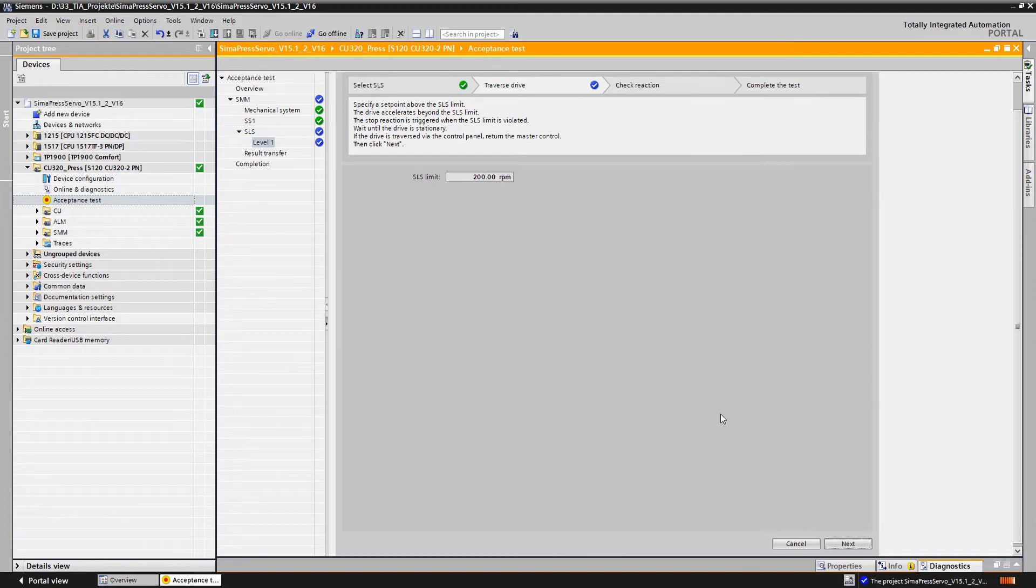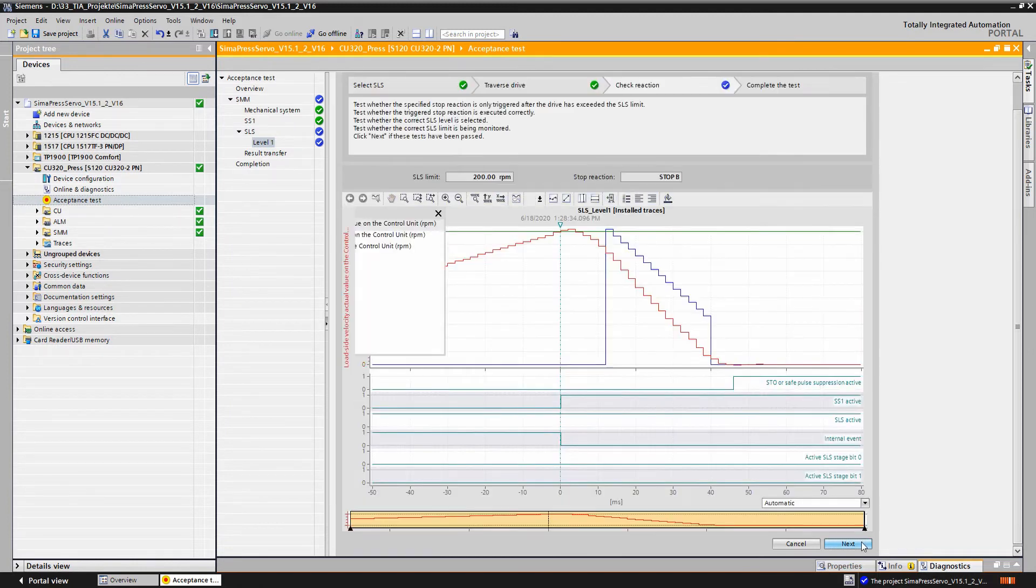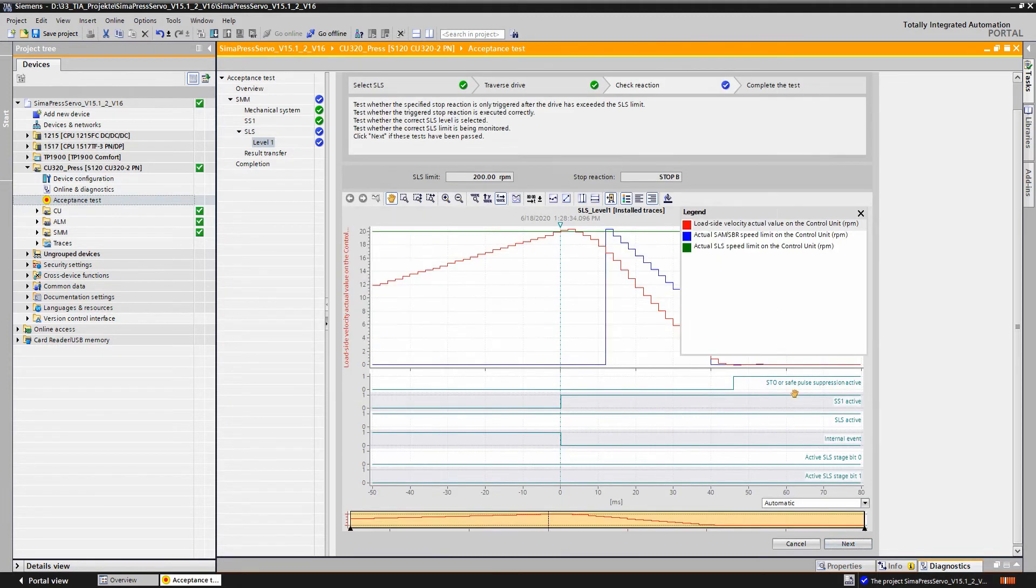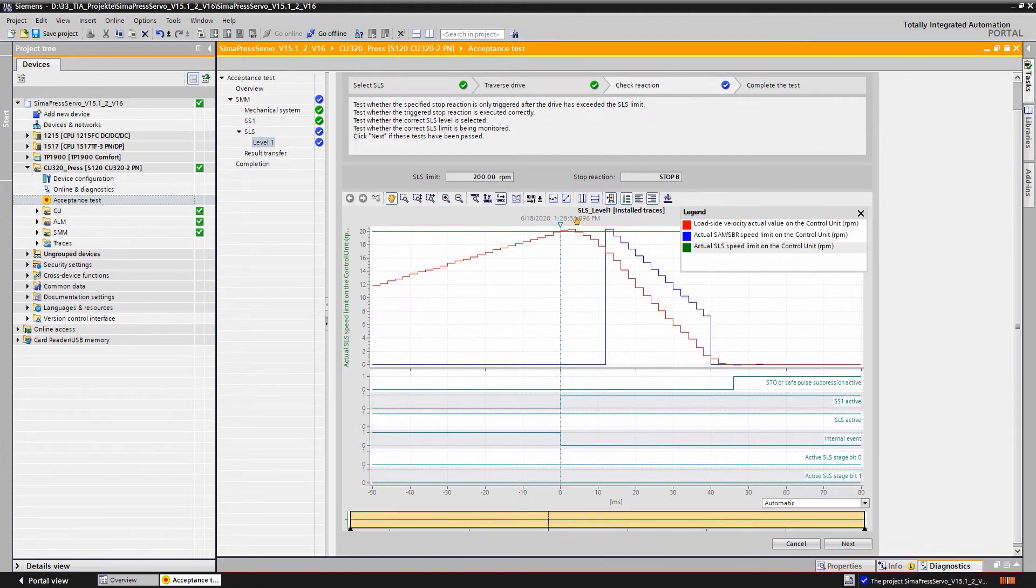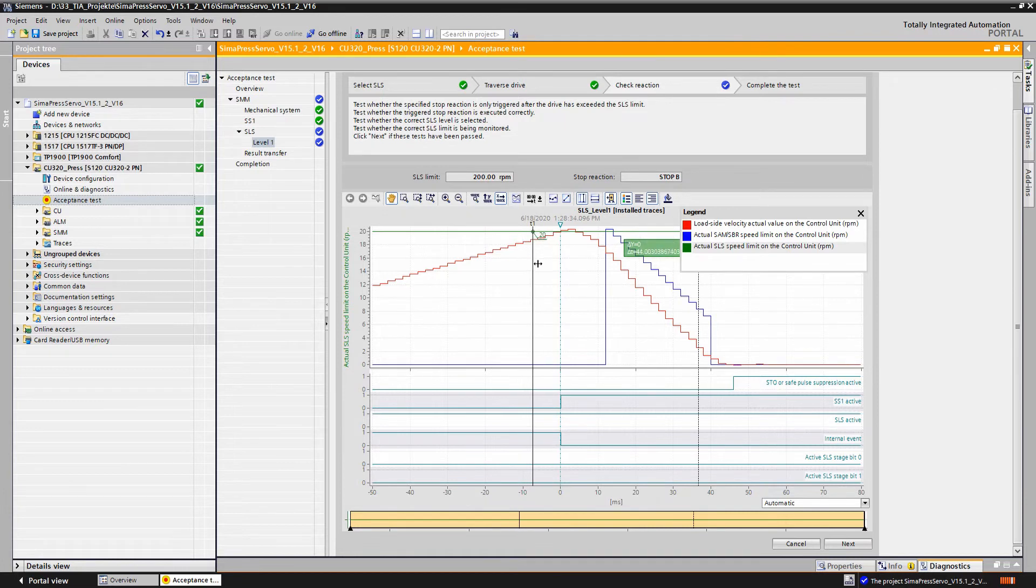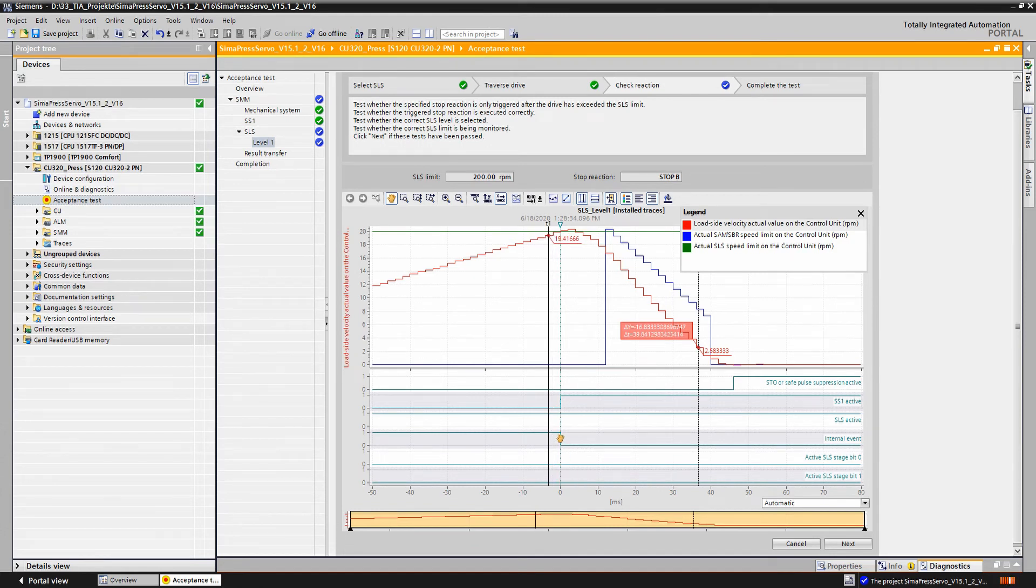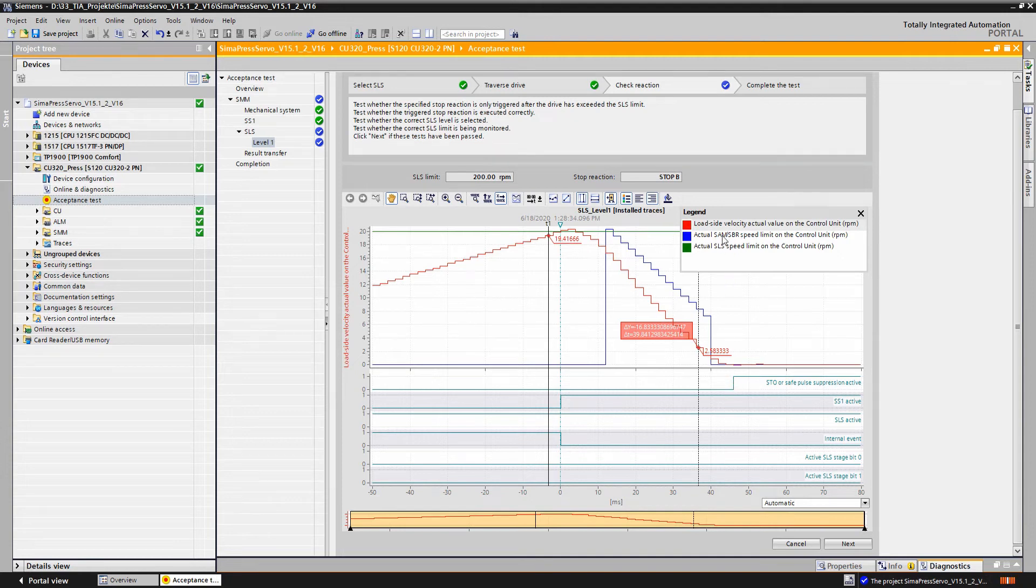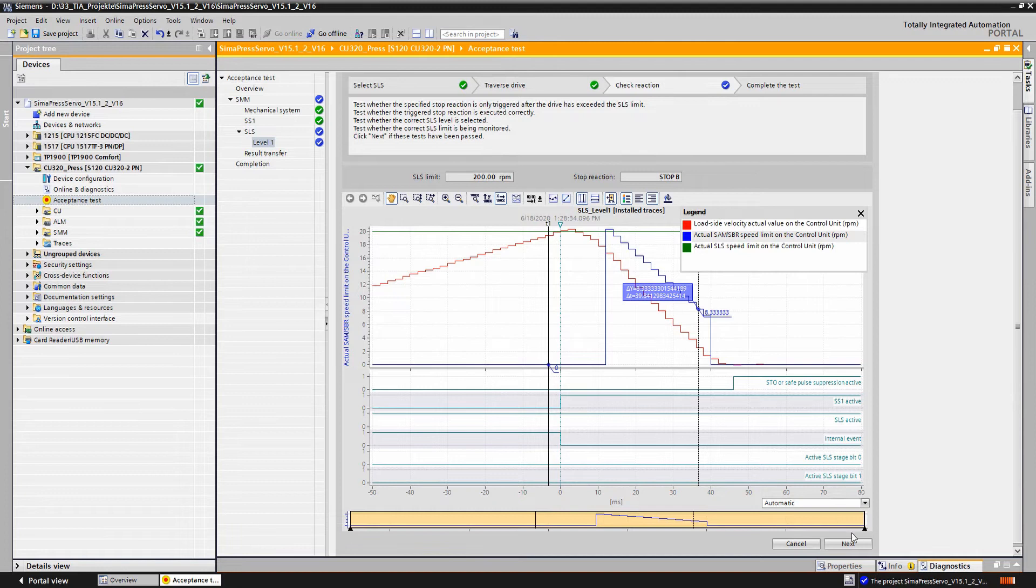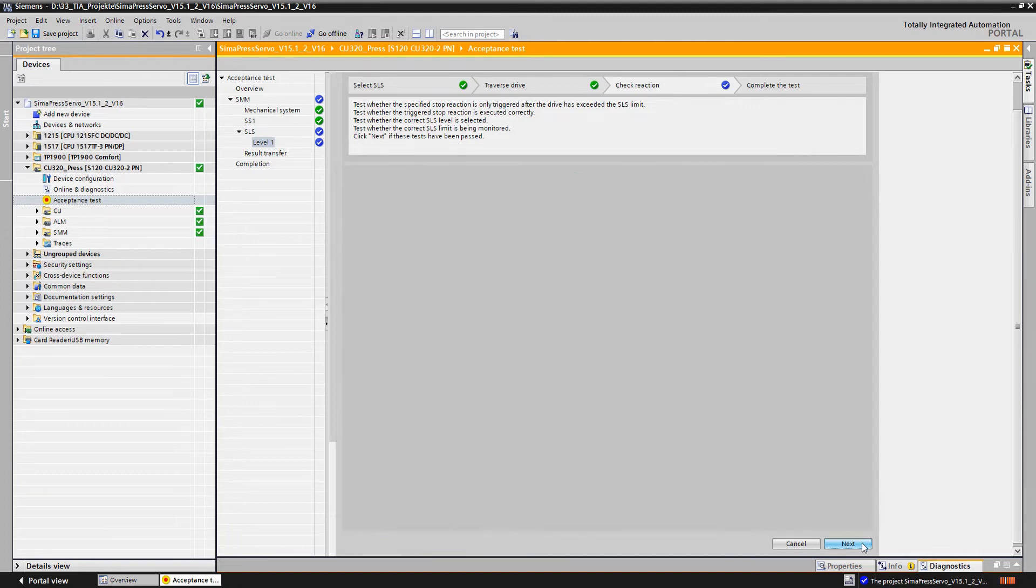Now we return to the trace analysis. We check whether the drive is deactivated at the speed limit defined in the specification, whether the correct SLS stage has been selected and whether the shutdown procedure is carried out correctly after the stop reaction has been carried out. In other words, whether the drive is braked to a standstill as before in the SS1 test and does not coast down beforehand. And if all these criteria are met, we click to continue.